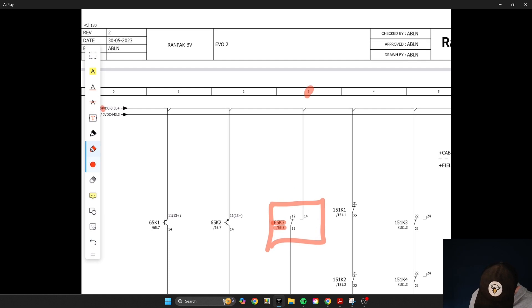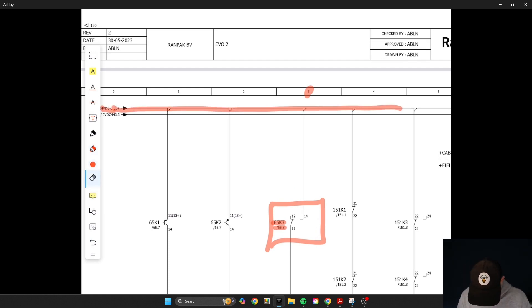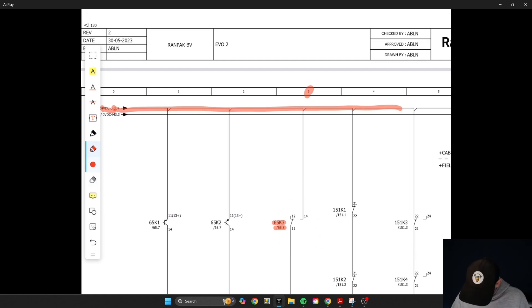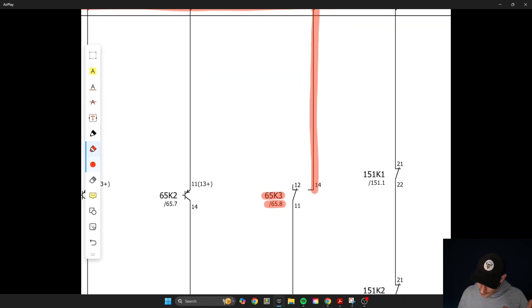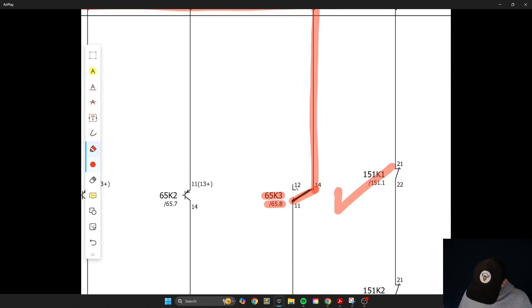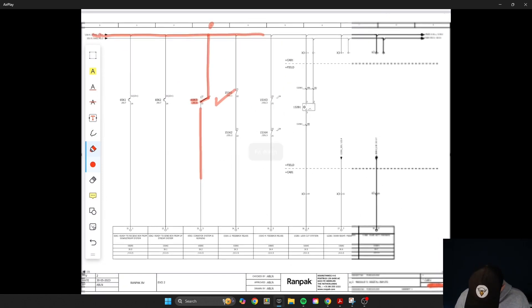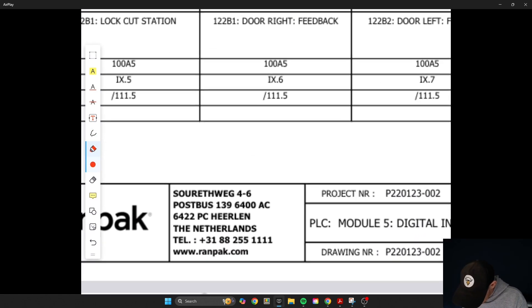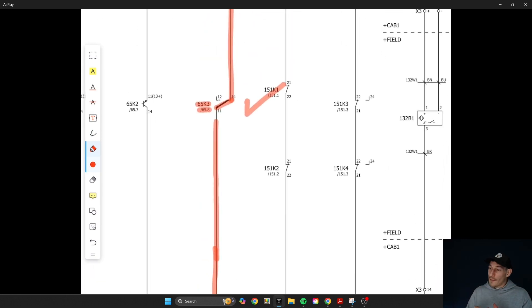You can see a 24 volt feed coming along here into the normally open contact, and when that coil side of the relay energizes it switches that contact over, which allows 24 volt DC to flow through the relay and down here into a PLC module digital input. So that's just a different way of referencing relays within two different styles of electrical schematics.